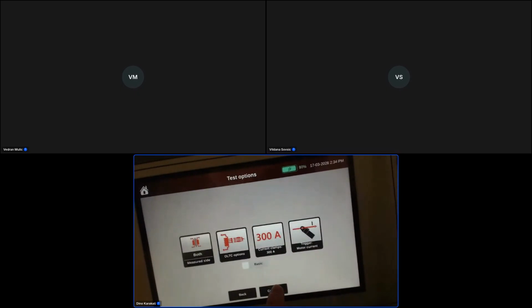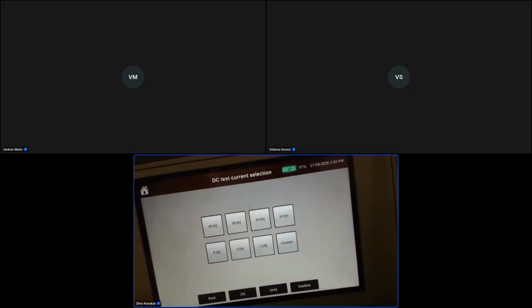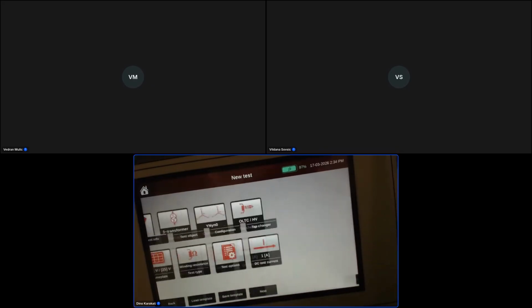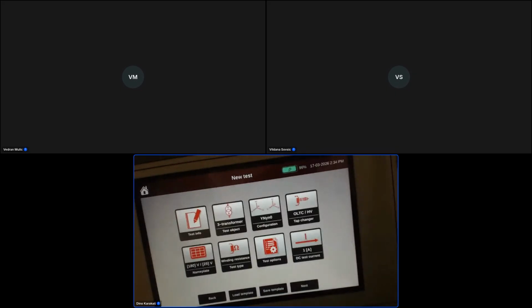Test options, this is something we already did. We select the DC test current. It can be in milliamps or in amps. For this transformer, 1 amp is enough, so we'll select 1 amp. And we can save this template as winding resistance.